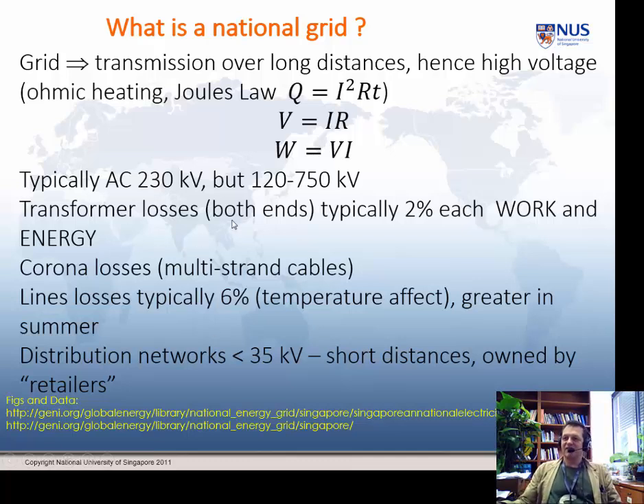Okay, I won't talk about transformer losses. Effectively, it's work and energy. So if you go past a substation, you'll hear the humming. That's losing energy. There's energy going to making that noise. That's part of the losses of transformers. Corona losses. If you've ever stood under a power pylon when it's raining, you can sometimes see it sparking or hear the psst noise. That's corona arcing. And effectively what you're doing is you're ionizing the air in close proximity to the insulators. One way of reducing that is multi-strand cables, which are widely used, but there's no getting away from it when you're using the sort of voltages that are in the national grid.